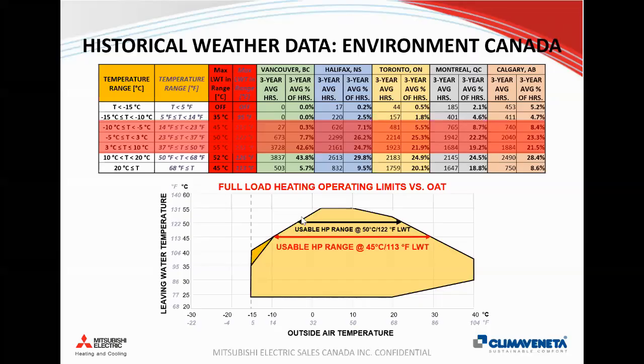So if we just build on that concept of a 45 degrees Celsius leaving water temperature from the heat pump and -10, this means that if you use a 45 degrees Celsius supply temperature, you can run off the heat pump as low as -10 and as high as about 28 degrees Celsius. Or if you're looking at condenser loop systems or in-floor radiant systems, this means that you can use the heat pump from -15 to +40 at all times with a 30-degree supply. So again, just minimizing the design temperature as much as feasible within your design will allow you to take better advantage of the heat pump.